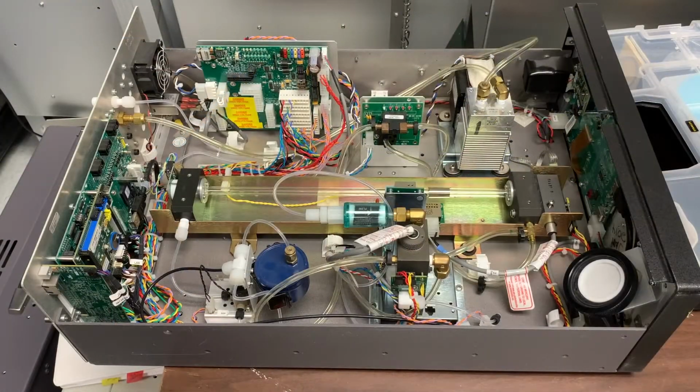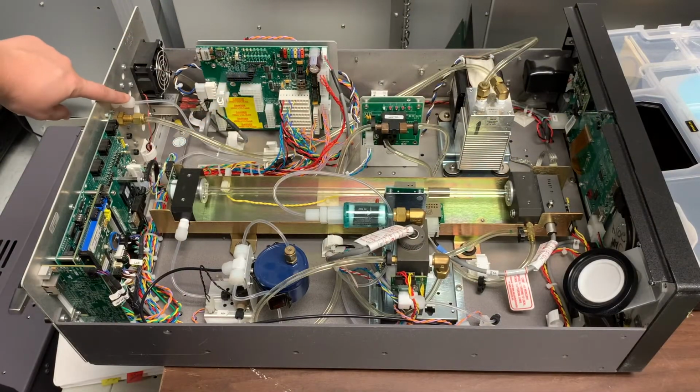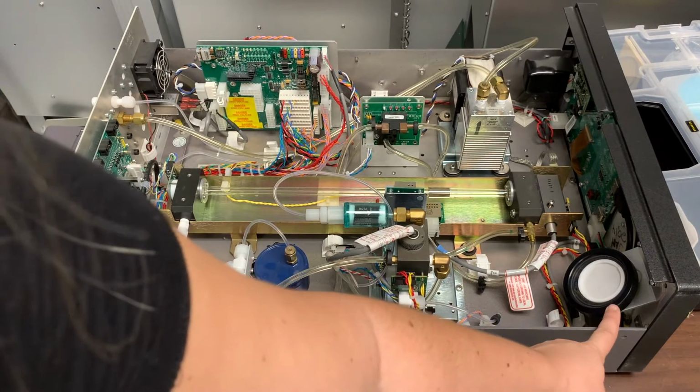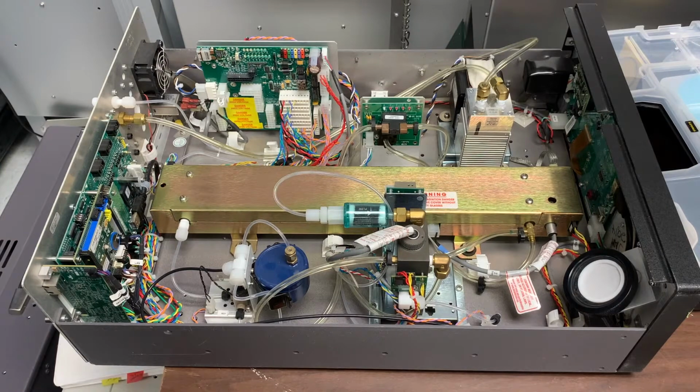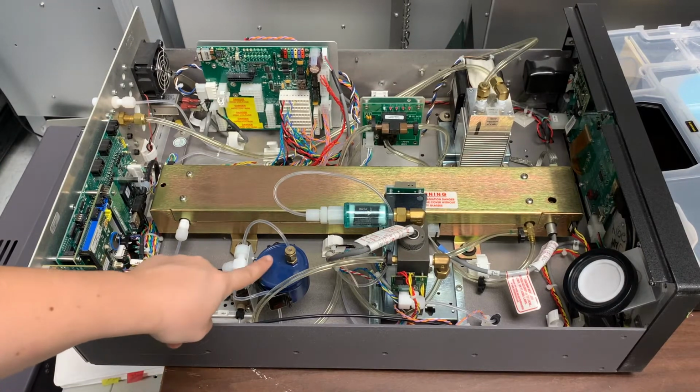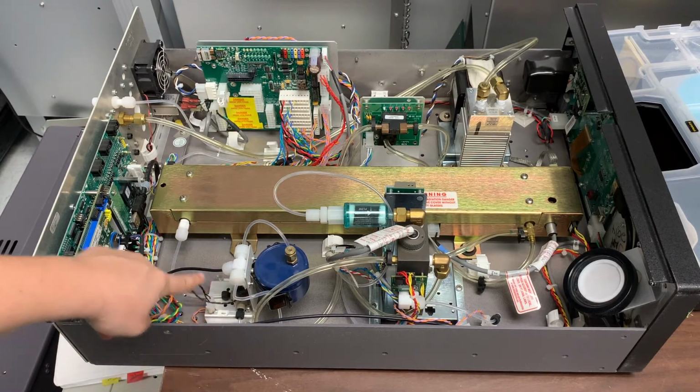Here's a closer look at an ozone analyzer. As air enters the instrument, it first goes through a filter to remove any dirt or dust caught in the airstream. Then the airstream is split. One stream goes through a scrubber that removes all ozone. A second stream continues unimpeded.